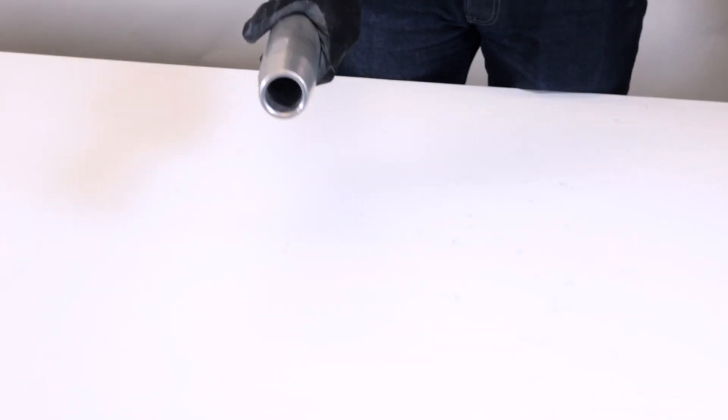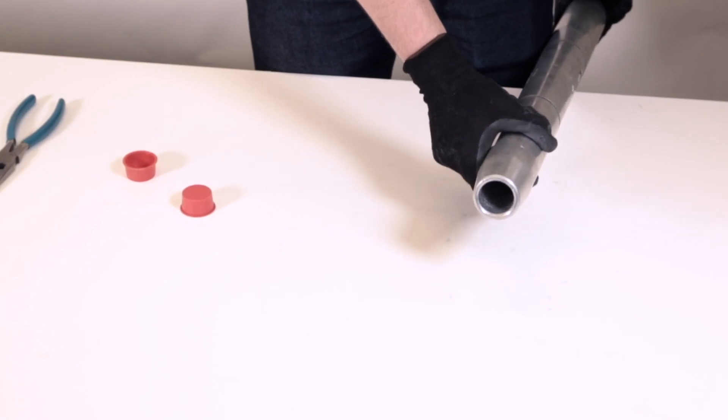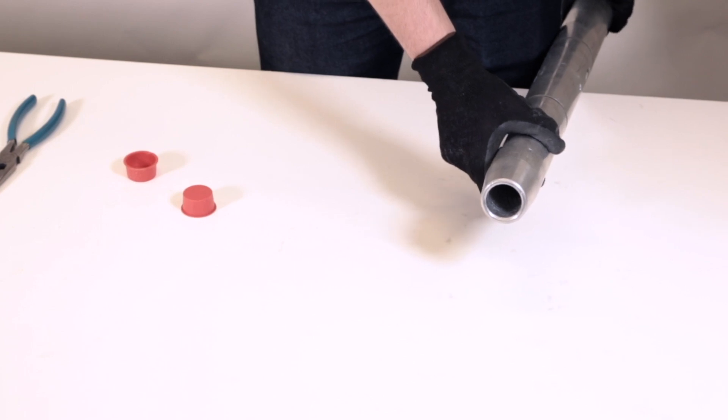Remove the plastic plug from the aluminum body and inspect the inside bores of the hardware to ensure that there are no sharp points or other defects. If flash or small aluminum bits are present, clear out with a spare piece of conductor.